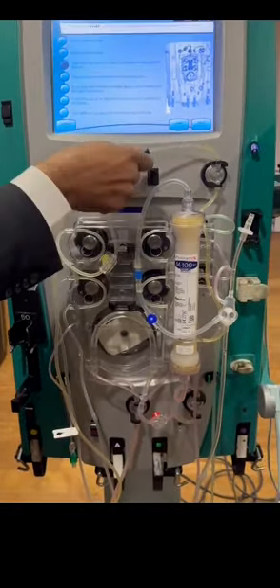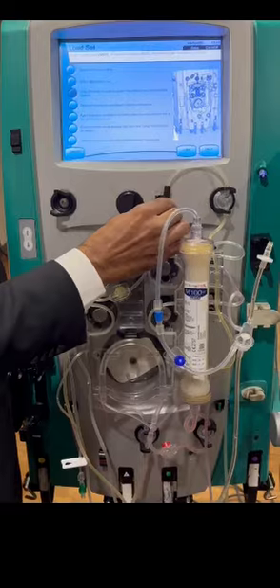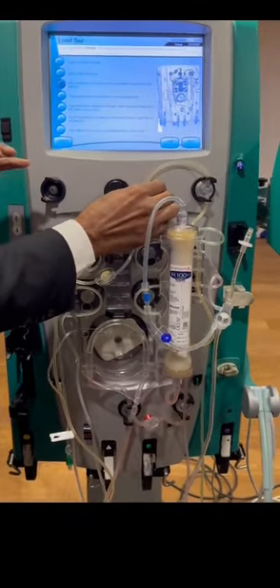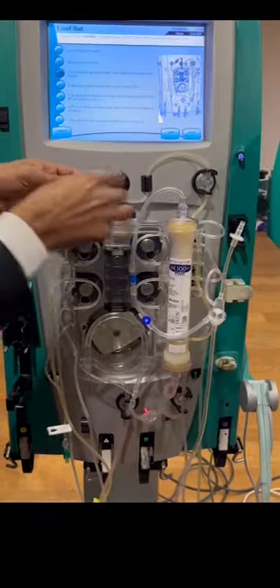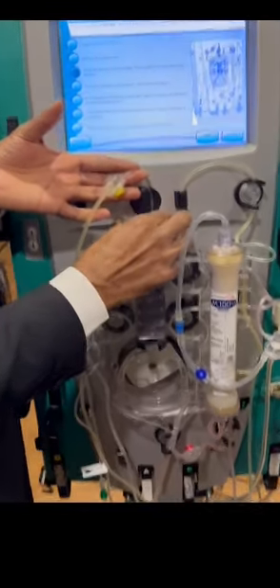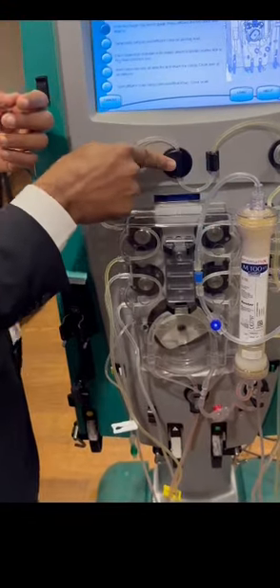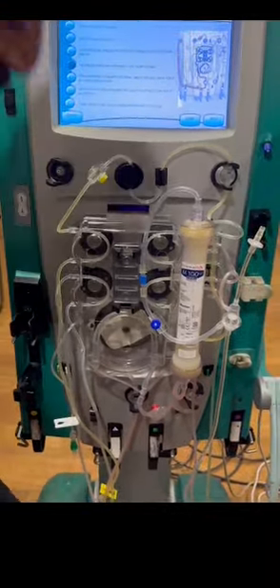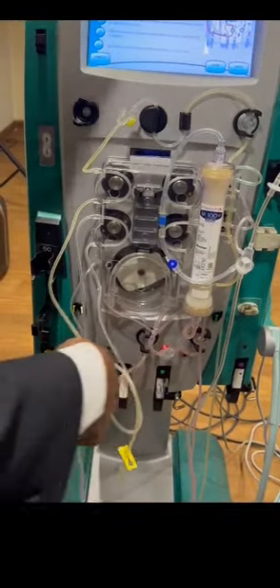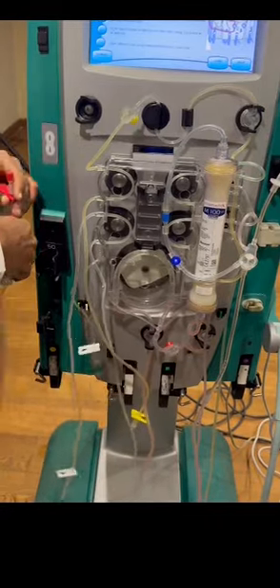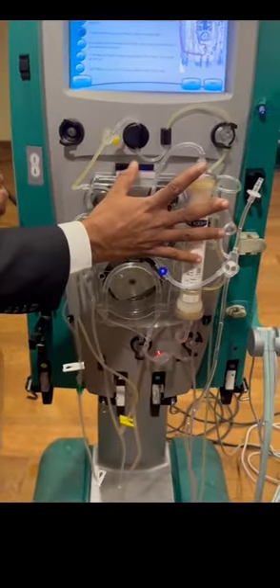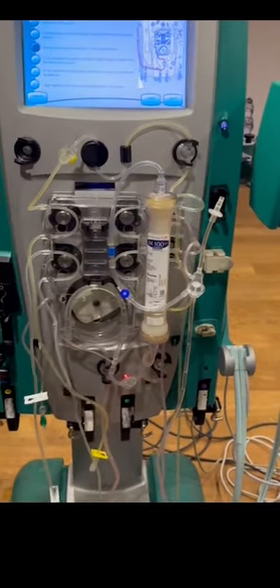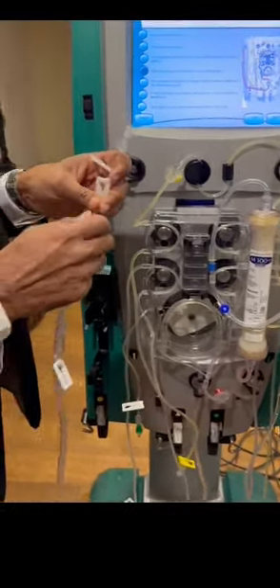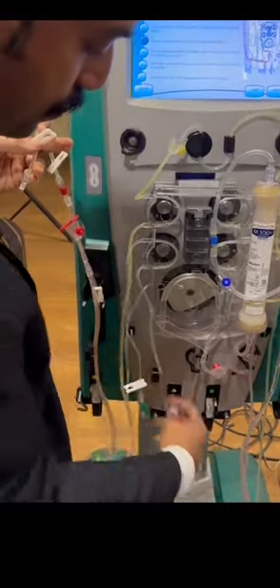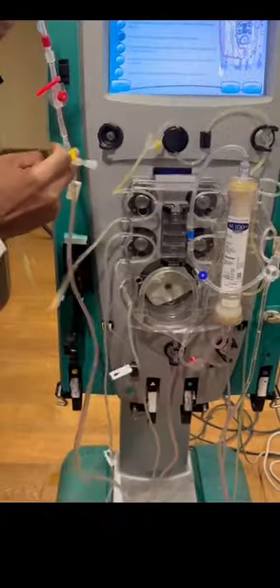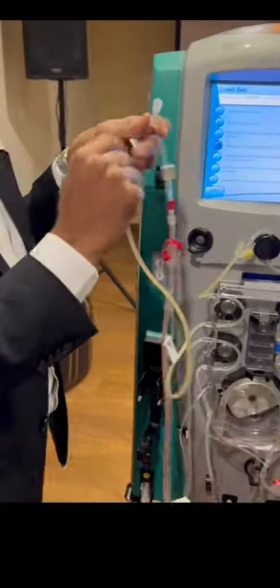Next the machine says snap the discharge ring. As I said, like earthing, we connect this yellow line in this direction. Then this is for the blood leak detector. In case the membrane ruptures, blood will be detected from here. Then temporarily hang. I need a drain maybe to empty this because I already primed. Then it says connect the access line and effluent line with a Y connector. It is just for connecting.